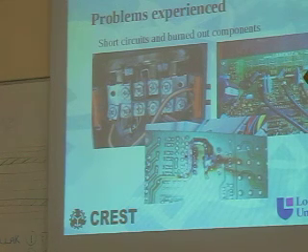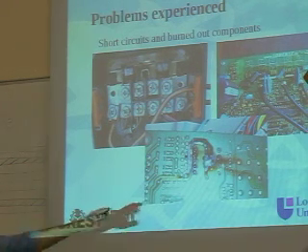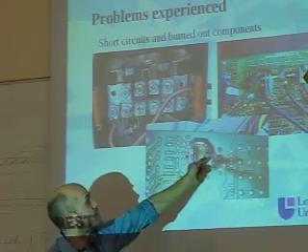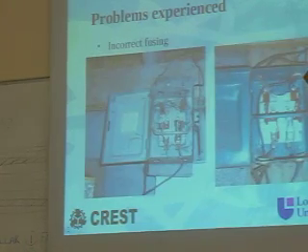I got there, wired it in, and within about 15 minutes of getting to the community, it had taken me a day and a half to get there, and I wired it in, I could smell kind of burning components, and I knew within about 15 minutes that I'd just have to come back again, and that was the end of that trip. So what happened was this was a rectifier for the power supply for this board, and they'd installed it the wrong way around. So it was a bit annoying.